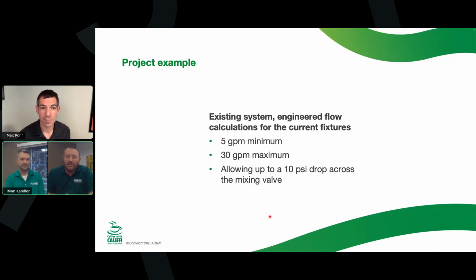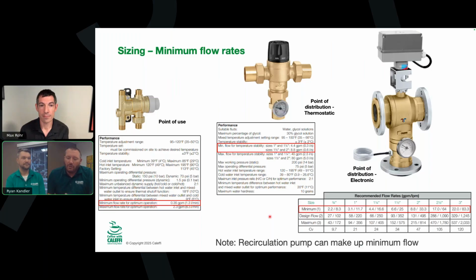That's one of the biggest tech questions that we have. If our Legio mix isn't functioning properly, it's always that recirc, and it's just not enough flow going through that mixing valve. Sometimes in a larger facility, if there's a leak or something like that, a lot of times the maintenance guy will open up a ceiling tile and just start closing valves. You could wind up with a recirc branch that's completely closed off, unbeknownst to everybody else, and all of a sudden that valve is hunting. You're not quite sure why. If you open up enough fixtures to facilitate that minimum flow, and it settles in, now you know that there's something either with the pump or somewhere else within that system that you're not getting enough flow.